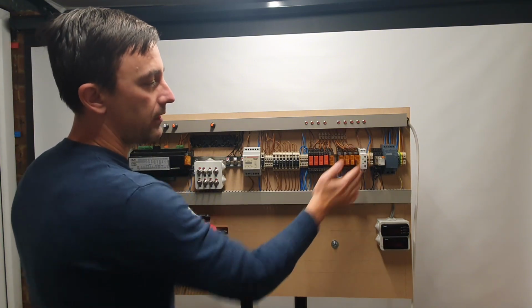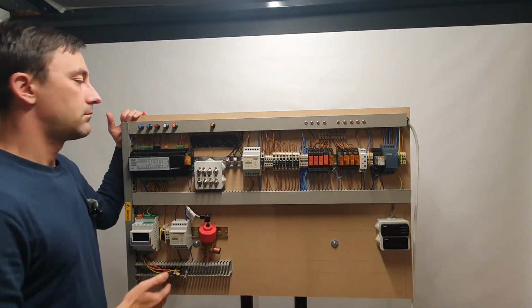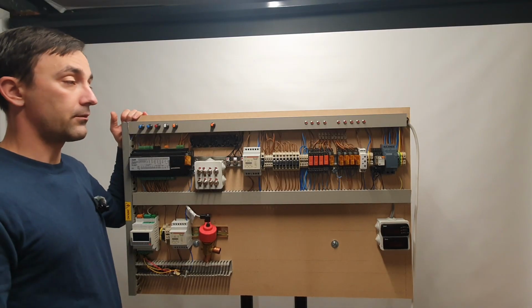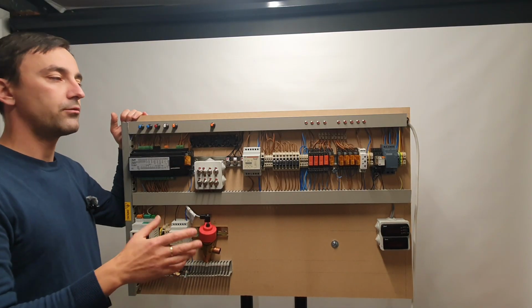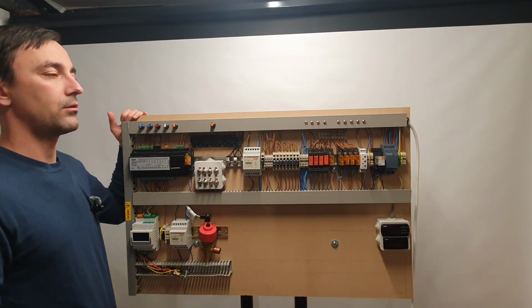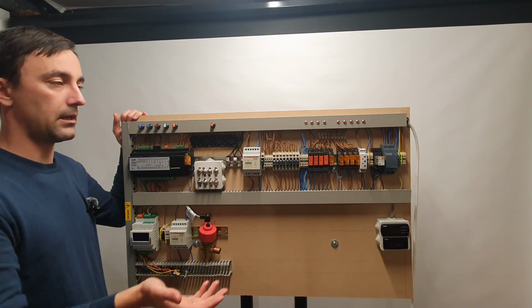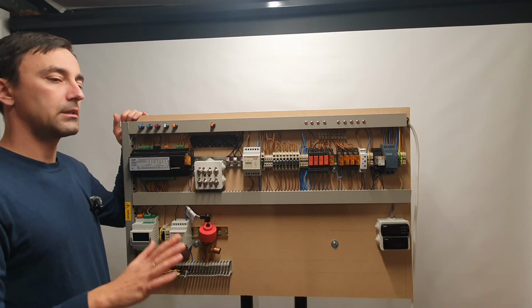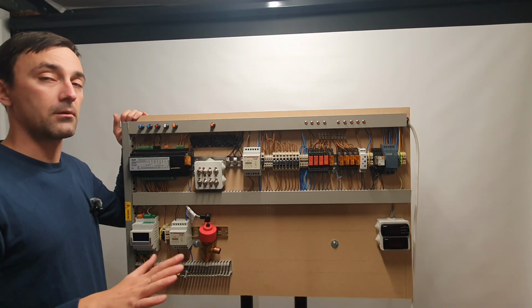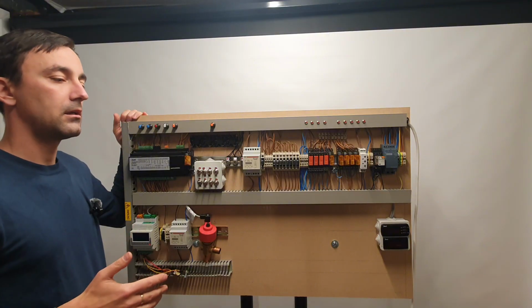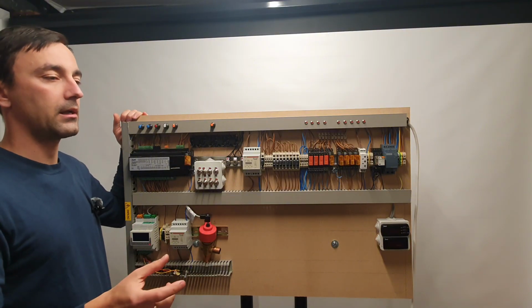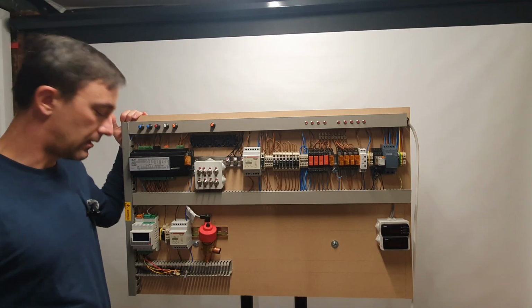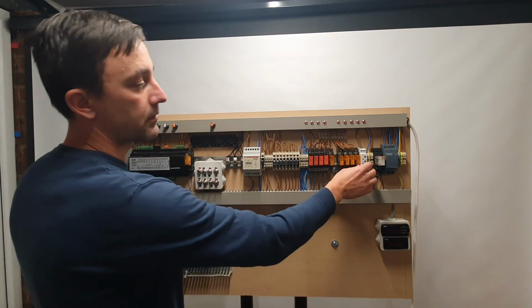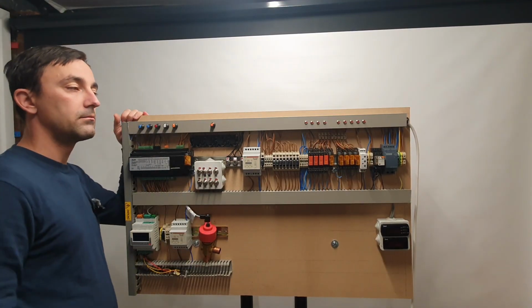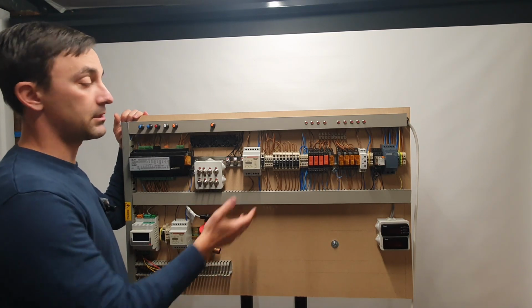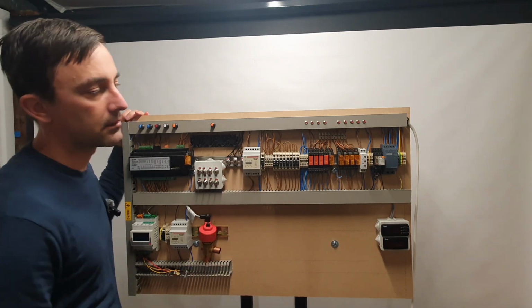We have a timer relay, purely because if you have a low liquid level alarm, for example, you want to wait for a minute or 2, or however long you want to set that, in order to make sure that it is an actual alarm, because sometimes things can happen a bit too quickly and it might generate a false alarm. So I decided to put a timer relay. It's quite common on bigger systems, especially on packs, to have timer relays in there.